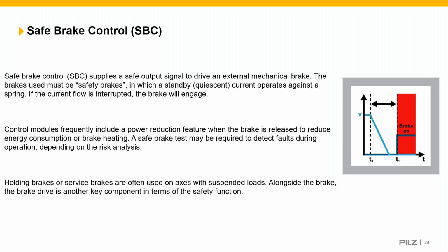Holding brakes or service brakes often used on axis with suspended loads alongside the brake. The brake drive is another key component in terms of the safety function. So the safe brake control function is normally initiated in conjunction with the safe torque off safety function. Again, so safe torque off appearing once more, but it just shows you where or how it should be used in conjunction with other aspects and not just on its own. So safe brake control will influence the entire brake management of the drive axis and should be coordinated with the purely functional requirements as well.